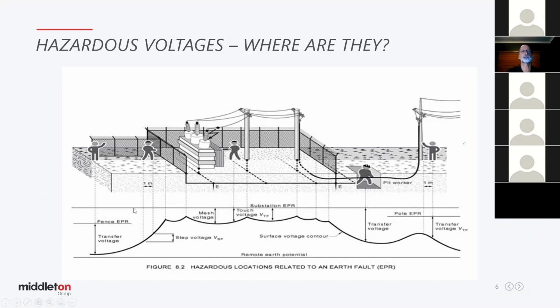In the graph at the bottom there, you can see that top line. And that voltage is in reference to remote earth, or some point far away, kilometres away, where the soil is at 0 volts. Potentially the supply point for this switch yard could be at that 0 volts. So this switch yard goes up in volts to what we now know as EPR. And as you can see from the graph here, if we measure the soil voltage radially away from the switch yard, it drops further and further towards 0. And therefore, the difference between the voltage at the switch yard, the EPR, and the soil gets greater and greater.